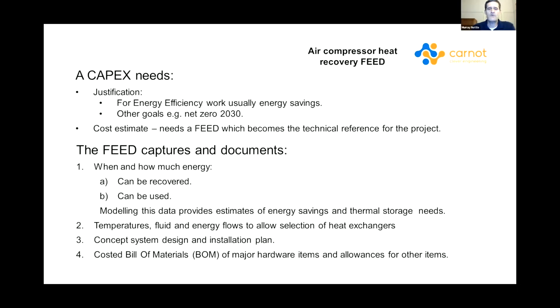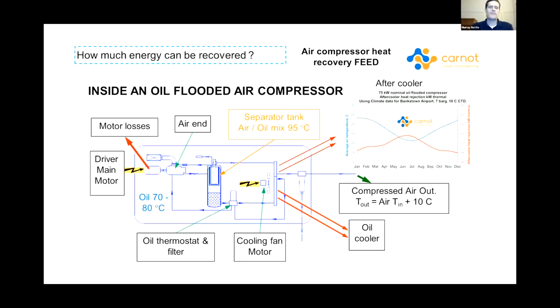So what's actually inside an air compressor and where all the heat flows? This is a generic drawing of an air compressor. The air comes in at the top left, goes into the air end, which is a compression module, gets compressed, and oil gets added to it. As we've heard with the refrigeration screw compressors, they inject oil there, same with an air compressor for most of them.